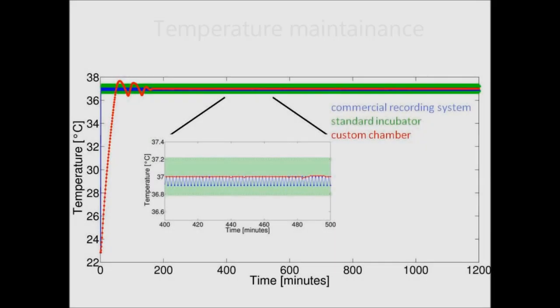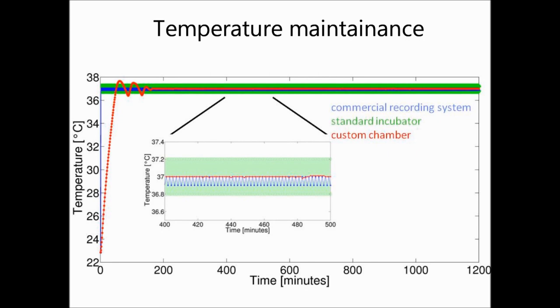The environmental chamber assured temperature control at 37 degrees in red, comparable to a standard incubator in green and to a commercial recording system in blue.